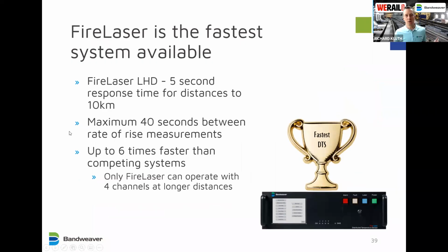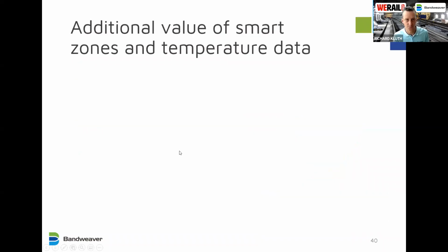And so with the fire laser, we have the fastest system available. It's a 5 second response time for distances up to 10 kilometers. That means a maximum of 40 seconds between rate of rise measurements. And this is up to 6 times faster than competing systems, which can take 30 seconds per channel at the longer ranges. So this means the fire laser is the only system that can operate at the longer range with 4 channels, which means you have more measurements, greater coverage per controller, and makes it a much more cost-effective solution.